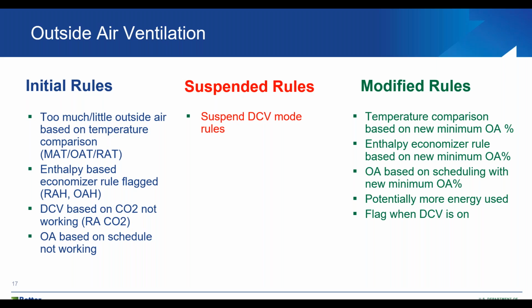There's potentially more energy used when we're operating with more air. The outside air rules have to be changed based on the schedule. So if you're changing it based on people coming in at 8 in the morning initially, and now it's people coming in at 10 in the morning, or not at all, you can change the rules. You can actually potentially save some energy as a result of not bringing in outside air if people aren't in the spaces. But the conditions need to be modified with the rules. Next slide, please.